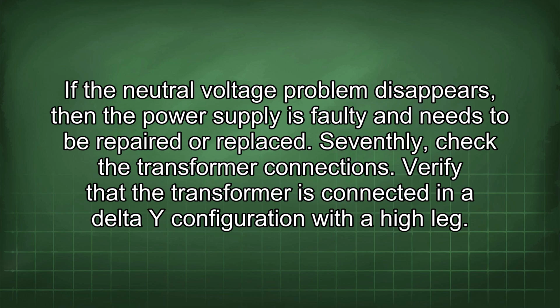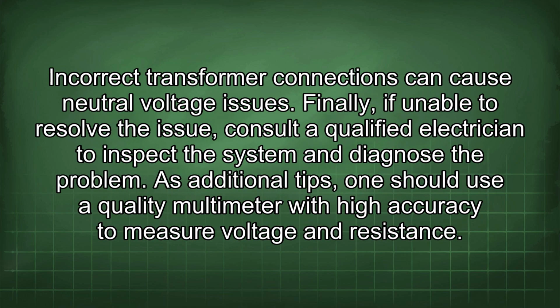Seventhly, check the transformer connections. Verify that the transformer is connected in a delta-Y configuration with a high leg. Incorrect transformer connections can cause neutral voltage issues. Finally, if unable to resolve the issue, consult a qualified electrician to inspect the system and diagnose the problem.